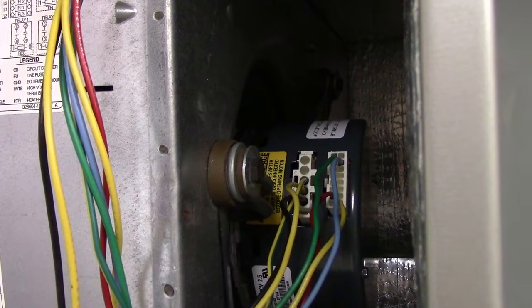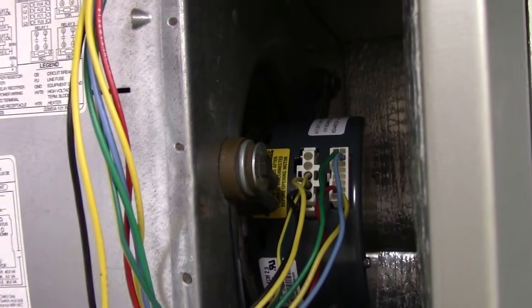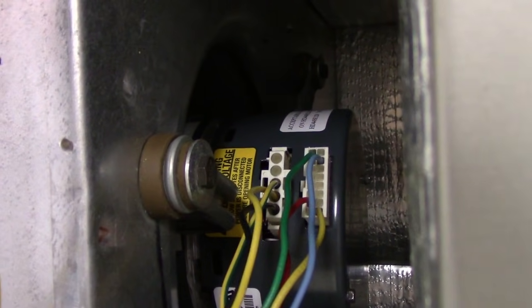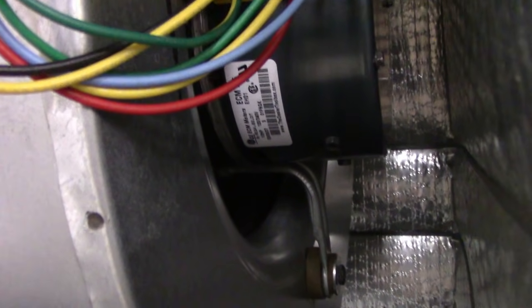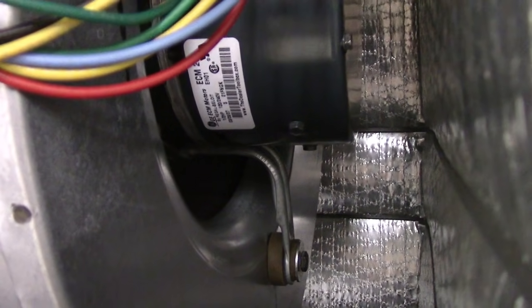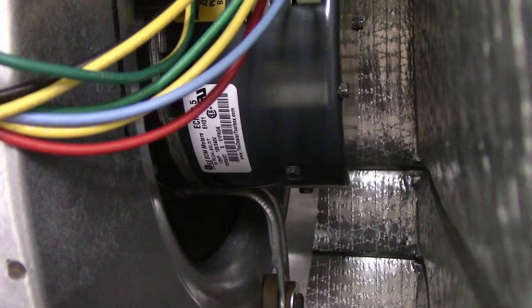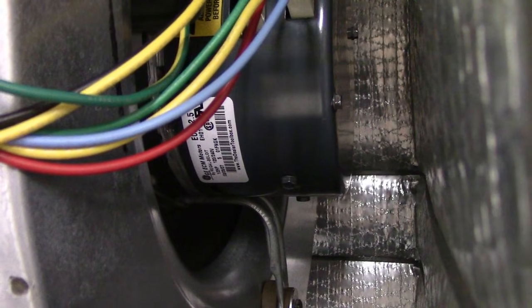Okay, we're down at the fan coil. I've got the inspection cover off, and I don't know if the camera's picking up this noise, but the motor's just pulsing. It's not turning the squirrel cage inside. It's just making this rumbling, pulsing noise.